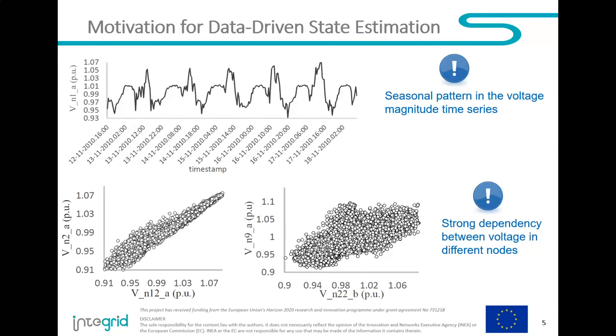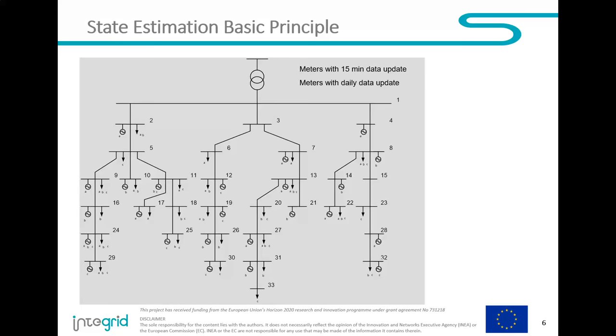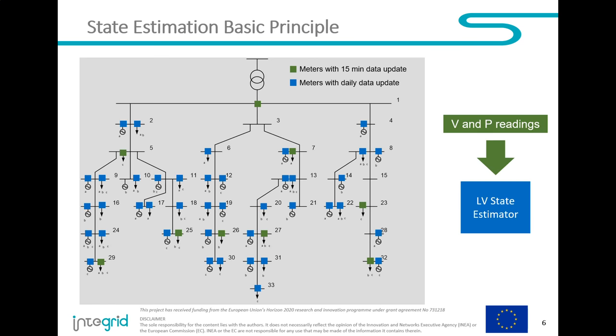This is real data from a real low voltage network in Portugal. In this scheme, you want to know the voltage at every node every 15 minutes, or every minute if measurements are available that frequently. You cannot have this for all nodes — the amount of information is high and communication cost is also high. Only GPRS can achieve this, and even then you have missing values. So in green we have a few meters — about 10% — with real-time communication, and with the state estimator we can guess the voltage on the remaining meters in real time using only the green ones.